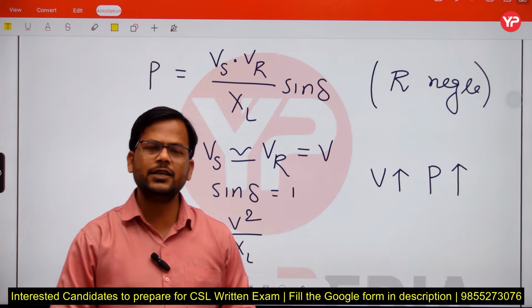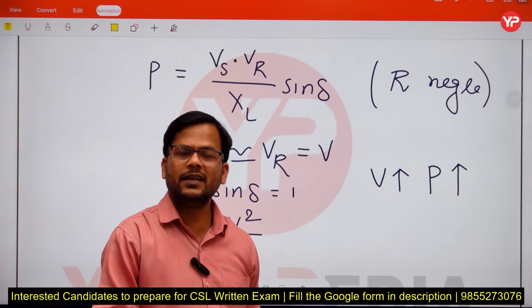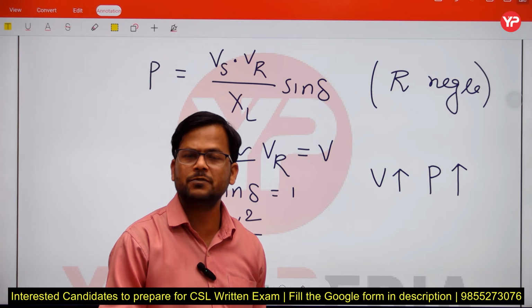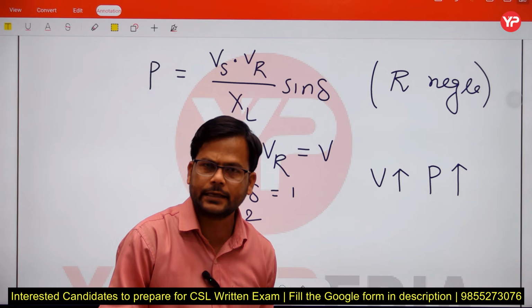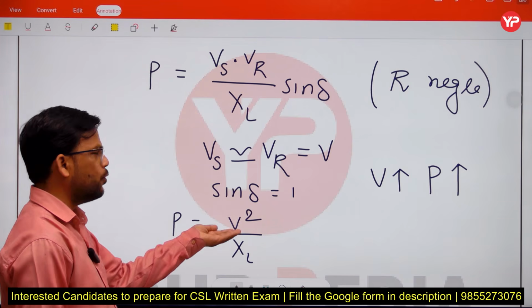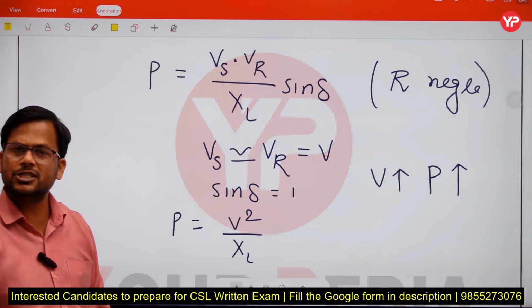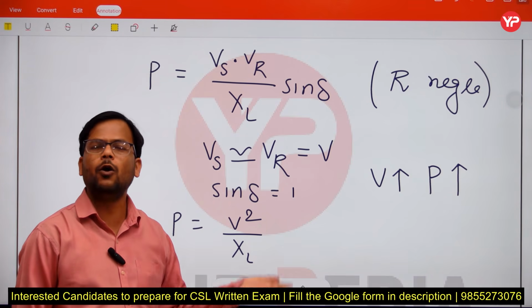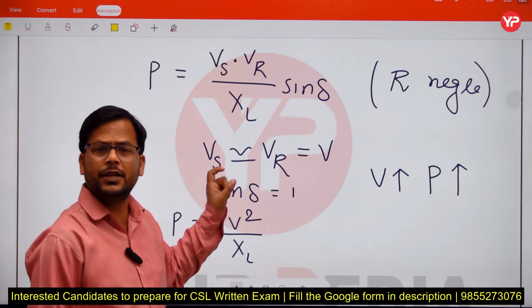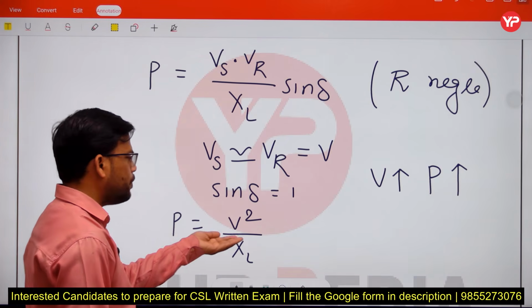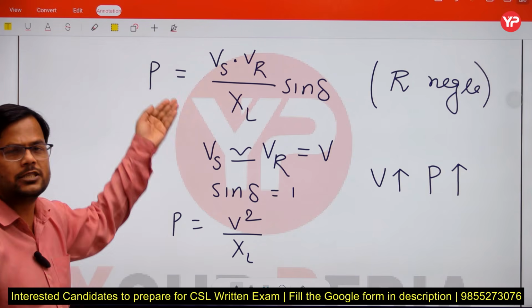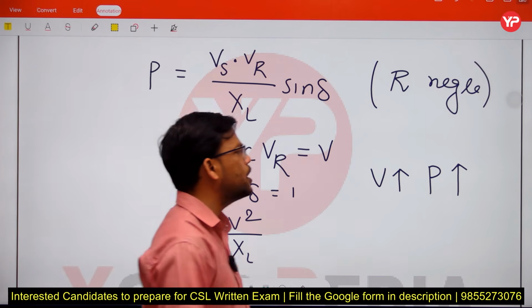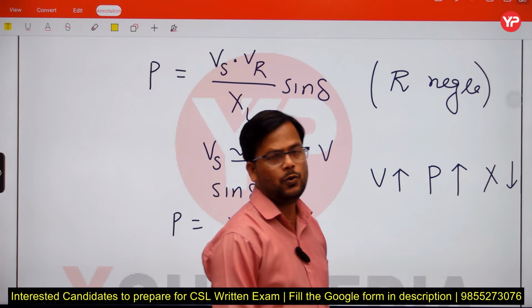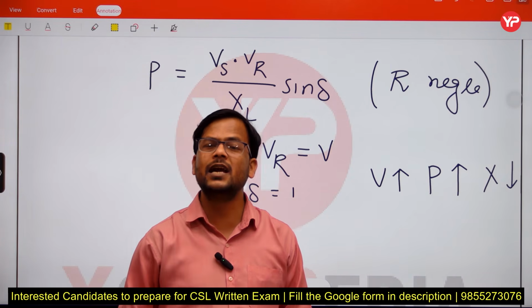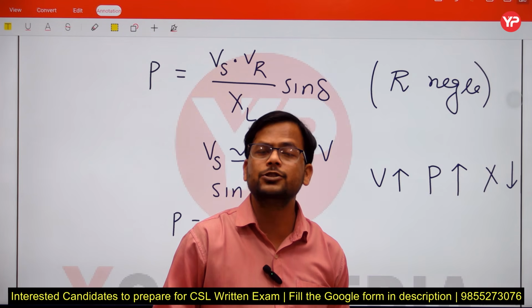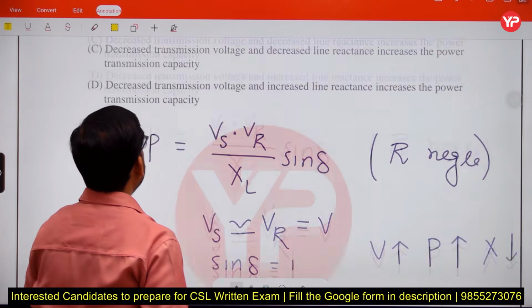But when engineers try to design a high voltage transmission line, they also care about the reactance of the transmission line, and their aim is to reduce the reactance. So, if the voltage level is high, then in this case power transmission is high, and the designer of the transmission line also takes care to reduce the transmission line reactance. So, if the voltage of the transmission line is high, then power transmission is high, but the reactance of the transmission line is low. Engineers always keep in mind that when we design a high voltage transmission line, we must reduce the reactance of the transmission line.